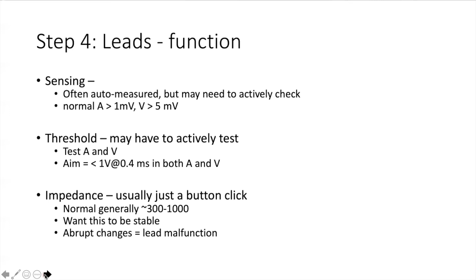This is something that you may want to get help from a senior fellow or EP fellow the first time you do it. But the goal is less than 1 volt at 0.4 milliseconds pulse width in both the A and V. And finally, impedance. This is in all devices, just a button click. Like I said earlier, you want this to be stable, somewhere between 300 and 1000, and abrupt changes suggest some sort of lead malfunction.